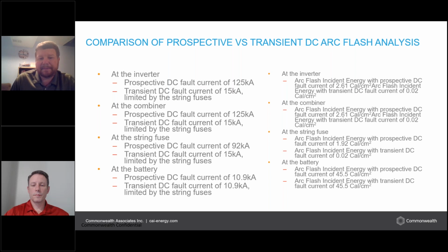So in this case, the DC arc flash wasn't terrible. You know, for those of us that work in arc flash, anything under 8 cals is generally something you can live with and work with because you'll be wearing reasonable amounts of PPE. But what we can see is by doing this DC transient analysis, we take it from having to wear arc flash rated PPE to not requiring that at all, by seeing that our arc flash basically goes to null. So going to a 0.02 incident energy level, that's much less than a category 0 level, so you can work in typical work clothes there.